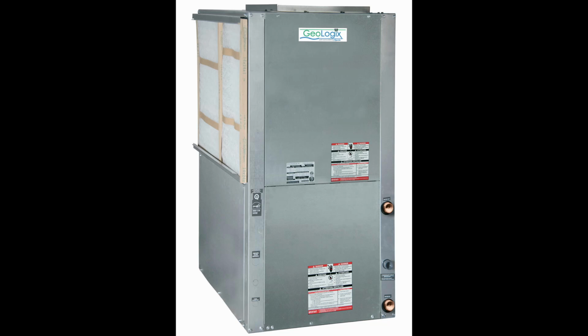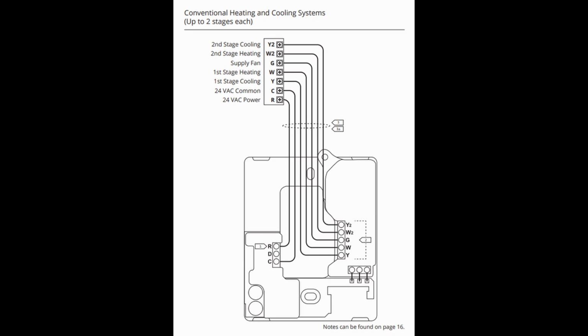When installing a thermostat on a water source heat pump, keep in mind the unit may not require the thermostat to control the reversing valve via the W1O terminal, as is associated with most heat pump applications. We sometimes find that the unit will require conventional wiring, and a logic board inside the unit will control the reversing valve to put the unit into cooling or heating mode based on the signals coming into Y or W. This is referred to as a heat pump wired conventionally. Wiring diagrams for either application can be found inside the manual provided with your Pelican thermostat.